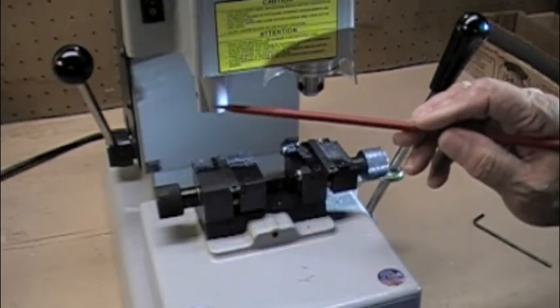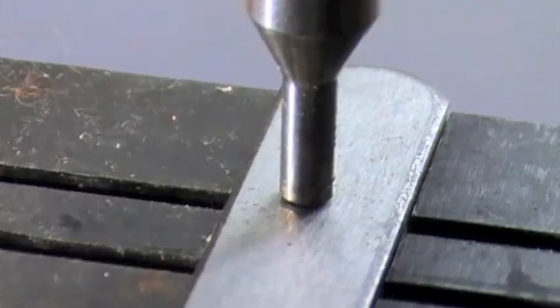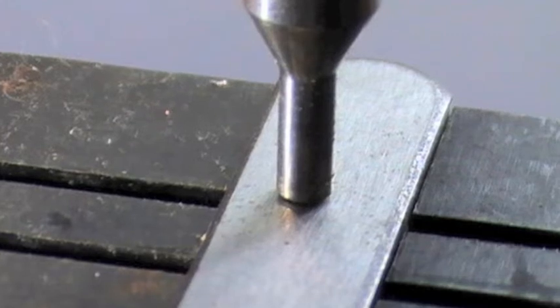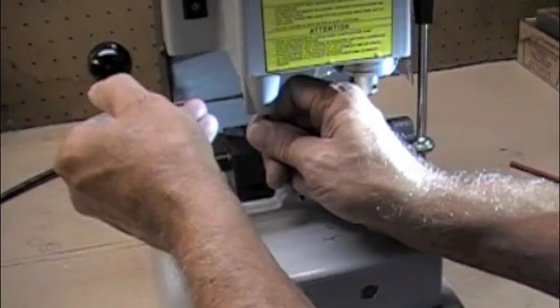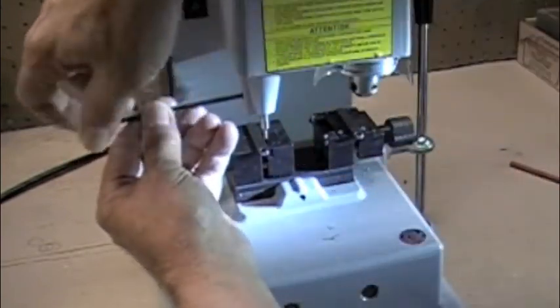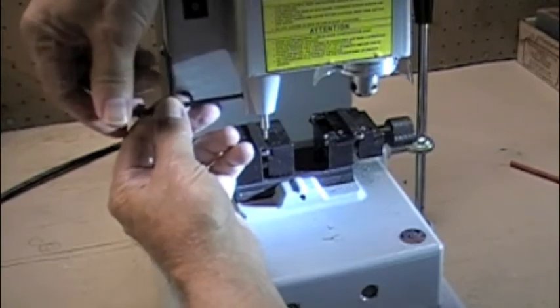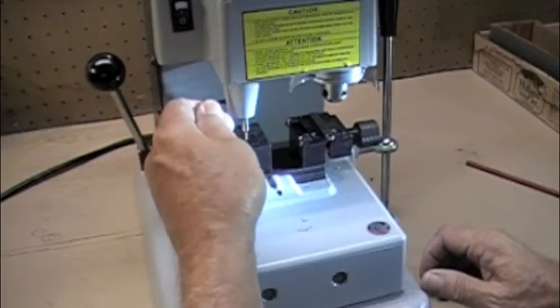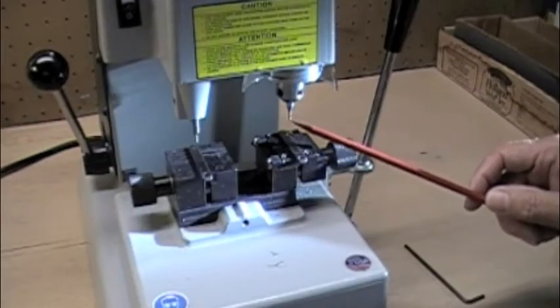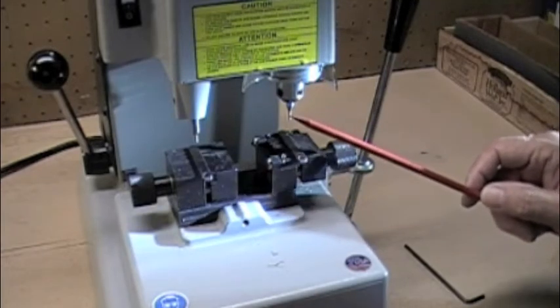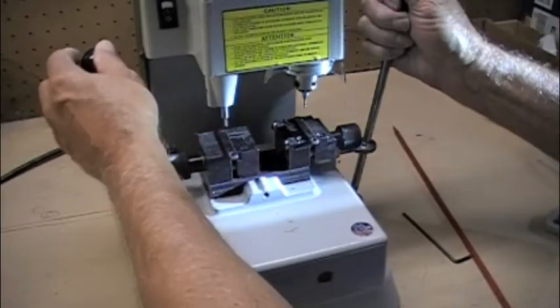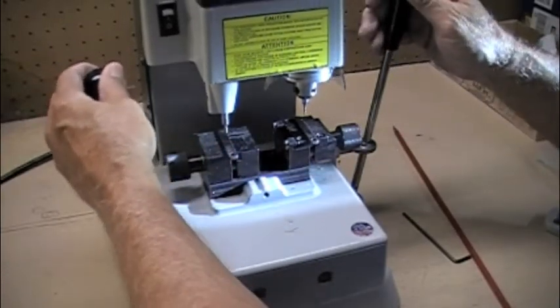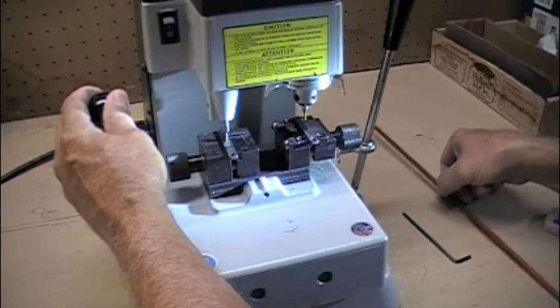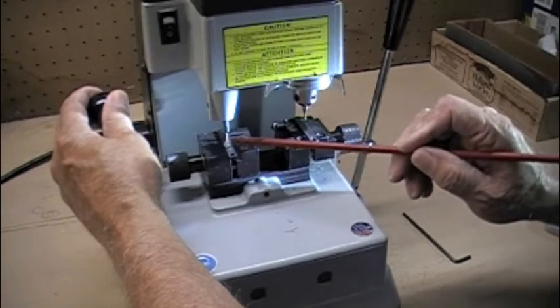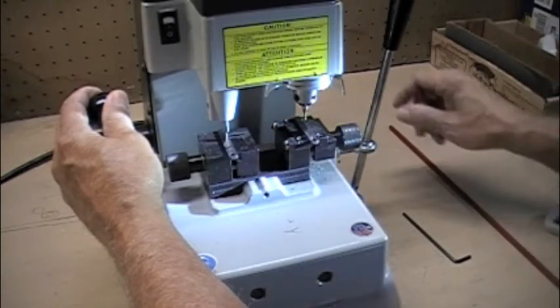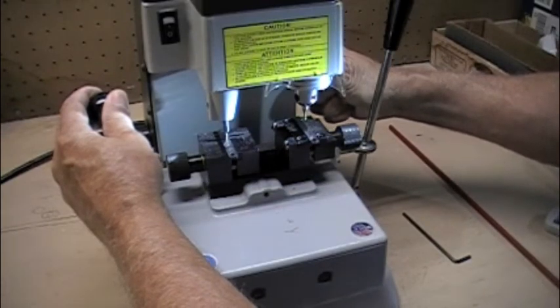This is only an aluminum housing that holds this, so we don't want to over-tighten this set screw. So here's a picture of the guide just barely touching the spacer. This is how it would look when you tighten the set screw. Okay, put the cutting bit in the jaw on the right and just barely snug it up, just enough to hold the cutting bit there. Go ahead and bring the cutting head down by using the lever on the left side of the machine. Bring the cutting head down just to where the guide just barely touches the calibration key on the left side. Then use the knob on the right side of the machine to lock the cutting head in place.